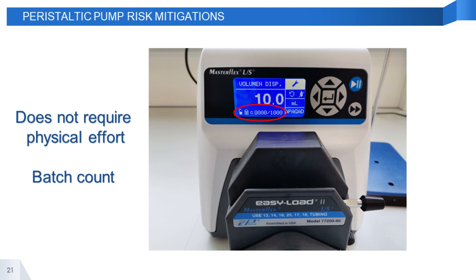In this operational mode, you select the volume you want to dispense, and you can also adjust some parameters such as the batch amount, which is the key to mitigate empty tubes. If the lot size is 1,000 vials, you just need to set those 1,000 in the pump through the display, as it is indicated in the photo there in the red circle. When the operator starts to dispense, the counter will move up its dispensation, and therefore the operator will always know how many containers have been filled.